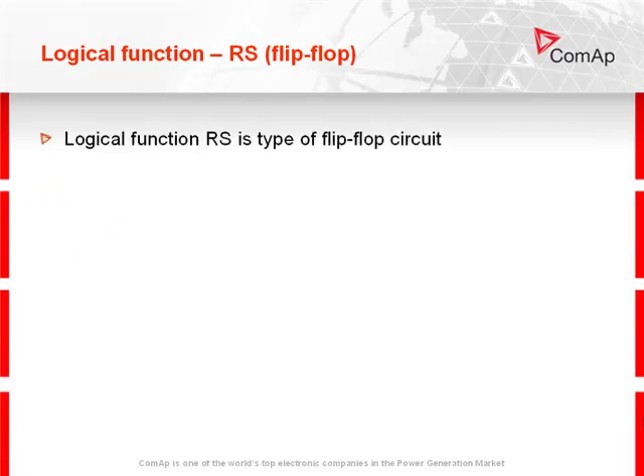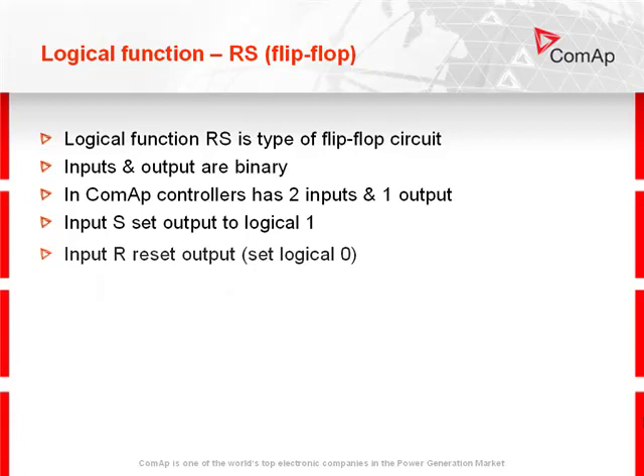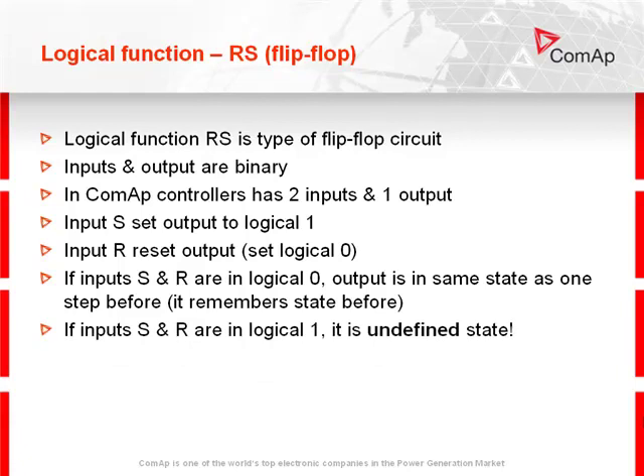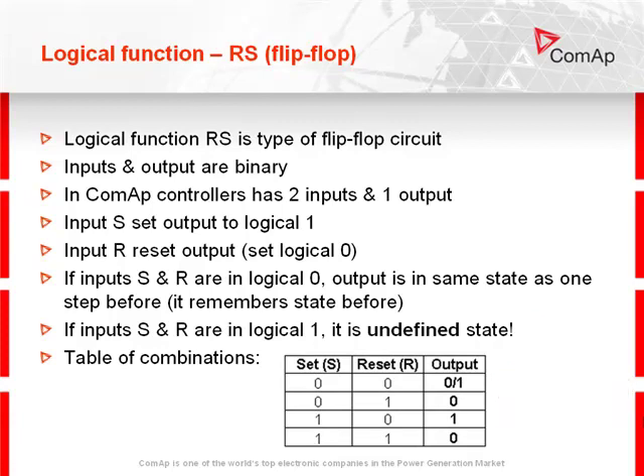Logical function RS is a type of flip-flop circuit. Inputs and output are binary. In COMAP controllers it has 2 inputs and 1 output. Input S sets the output to logical 1. Input R resets the output to logical 0. If inputs S and R are both logical 0, the output is in the same state as one step before — it remembers what was before. If inputs S and R are both logical 1, it is an undefined state; please don't use this state. In the table of combinations you can see what each input and their combinations cause.